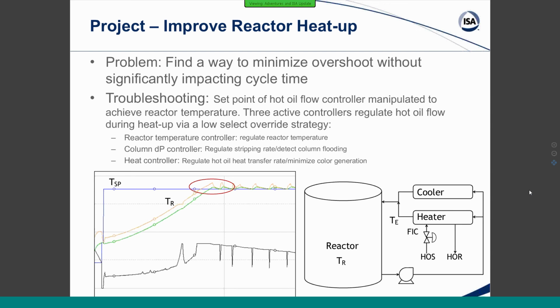A little more about this system. You can see the reactor down on the right. So the reactor has an external heating loop, goes through a heater or through a cooler, and the temperature of that is controlled by a flow control valve on our hot oil supply line. That valve is in turn controlled by one of 3 different controllers. Either the reactor temperature, or there's a column that you don't see that's on top of the reactor, and we have a DP controller on that to make sure that we're not flooding the column. And then finally we have a heat controller, a BTU controller, that helps us keep from boiling over everything in the reactor by heating it up too quickly. So of these, the logic would go through and do a low select strategy, so pick the minimum value of those and give that signal to our flow controller.